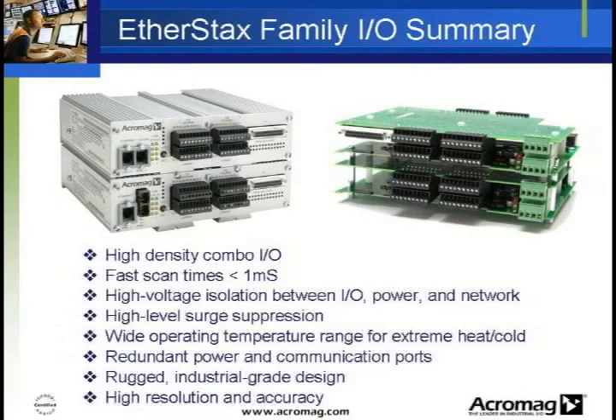Two DB25 input interface ports allow connection to Series 8B or 7B isolation amplifiers for virtually any analog sensor and providing high channel-to-channel isolation. A wide operating temperature range makes these units perfect for extreme temperature environments. Redundant power and communication ports ensure bumpless transmission in the event of a communication failure. And they are rugged with an industrial-grade design for high reliability operation and hostile environments.